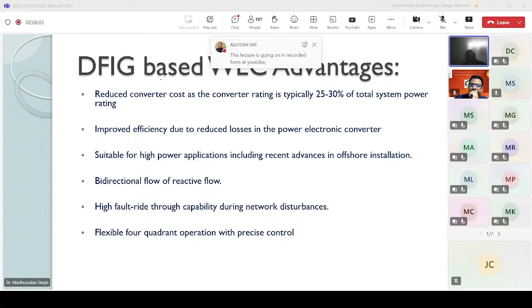The advantage is that if it is a DFIG based generation, the converter rating is typically just 25 to 30%, because you can transfer only slip power available in the rotor, which you all know happens to be S times PG. S happens to be the slip of the machine, so slip 30%. Accordingly, the rotor side converter rating reduces, right? Rating of converter reduces. Improved efficiency due to reduced losses in power electronics. Yes, we are operating at low power, 30%. Losses are relatively less. Overall operation is good. Suitable for high power applications, including recent advances.